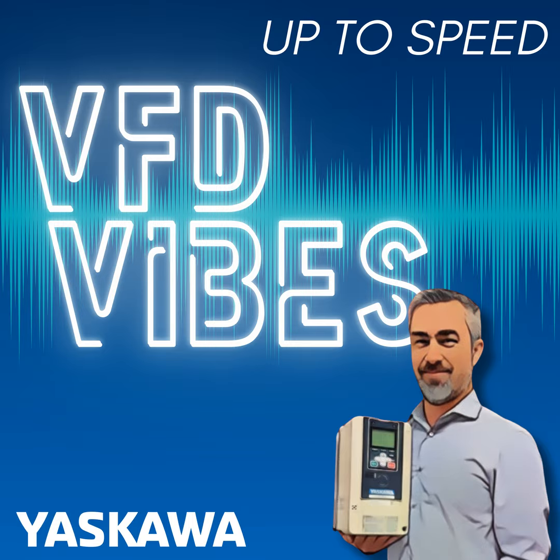So it's important to get the proper voltage. So I would always clarify, is it 208 or 230, 240? And hopefully they come back and say, oh, it was 208. 208 is probably 95% of the time what you're going to see out there, but 240 does exist. And then in regards to amperage, you always want to make sure that your rated output current of the VFD exceeds the motor full load amps. Yaskawa drives and many other manufacturers are NEC rated, National Electric Code, for motor horsepower to amperage.